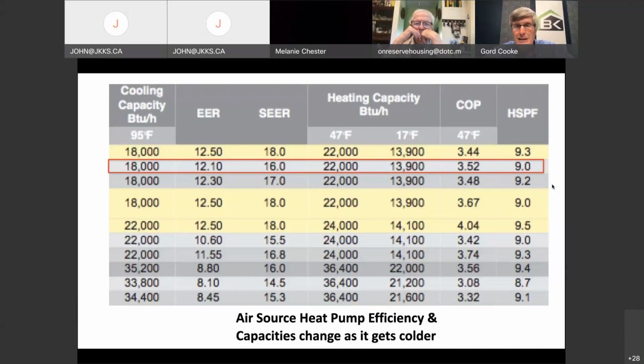This is the traditional heat pump, if you will. If I go down to the next red line and over to the right again, if I needed 22,000 BTUs at 17 degrees Fahrenheit, I actually have to put in a 3-ton system. So you think you only want to put in a 1.5 ton system, but because the heat pump doesn't get you that capacity at its coldest temperature, you need more. If you're in Manitoba, you're going to say we get colder than 17. I know you do, so it would go down even further.